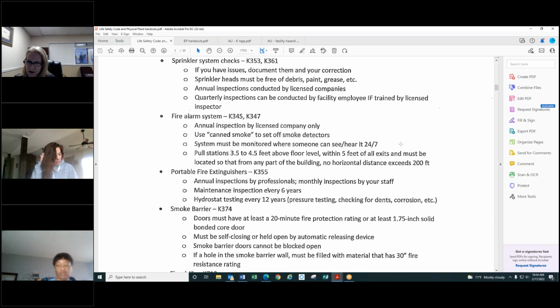Within less than 24 hours, fire alarm goes off. Our panel tells us it's at this pull station. We go to the pull station, and then here sits my precious sweet resident. And I'm like, oh, why'd you pull the pull station? She said, it said pull. Like, yes, you're right. So we ended up putting covers on all of ours, with the bar that can break the cover, but just know your folks and what may happen there.